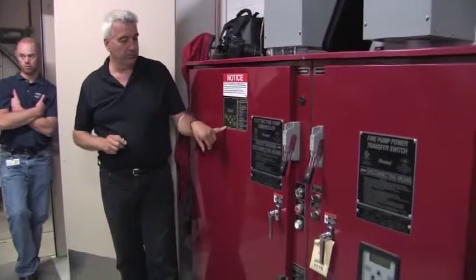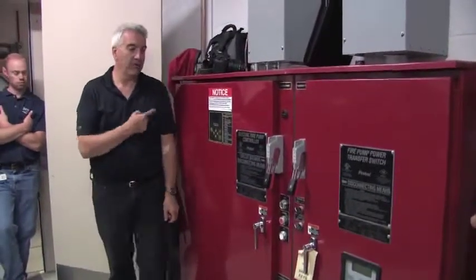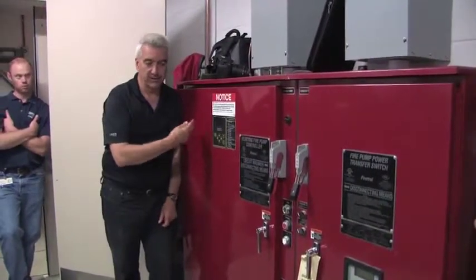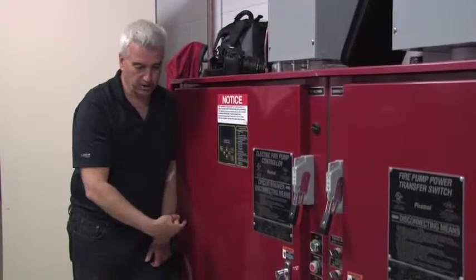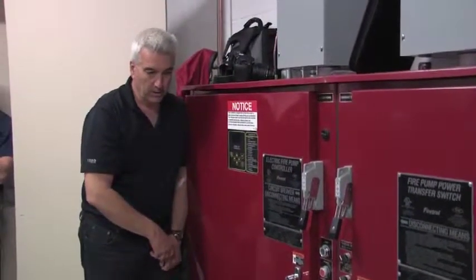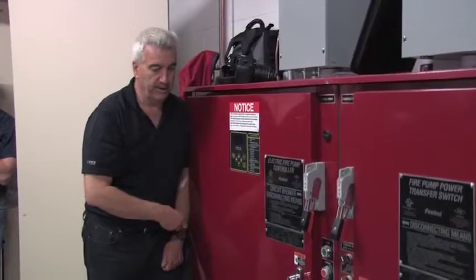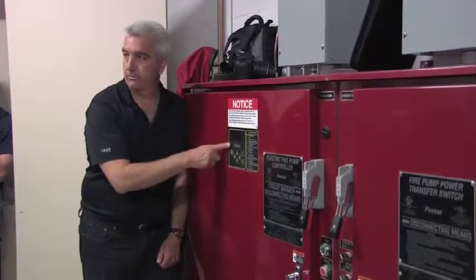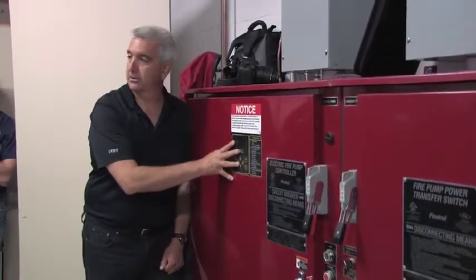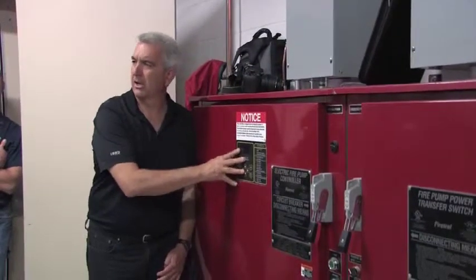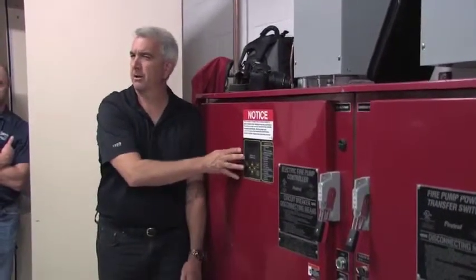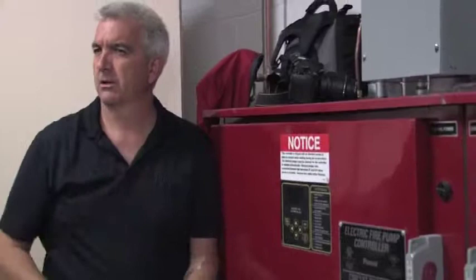These controllers have the ability to store 3,000 events. An event is anything that happens, like a start push button, a pressure call, or a loss of power; it'll record that. It records every hour. I don't know if you guys have had use for these or have had to look through any histories yet. I'm sure you get these elsewhere on the campus, don't you? The Mark II controllers? Quite sure. No? I don't think so. Well, we need to start changing them out then.